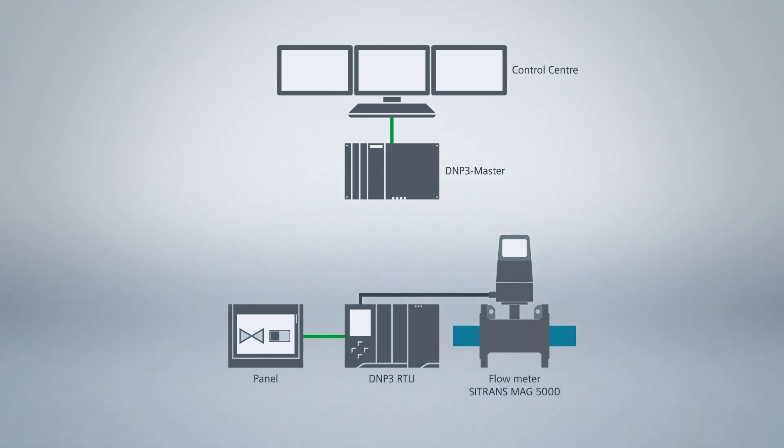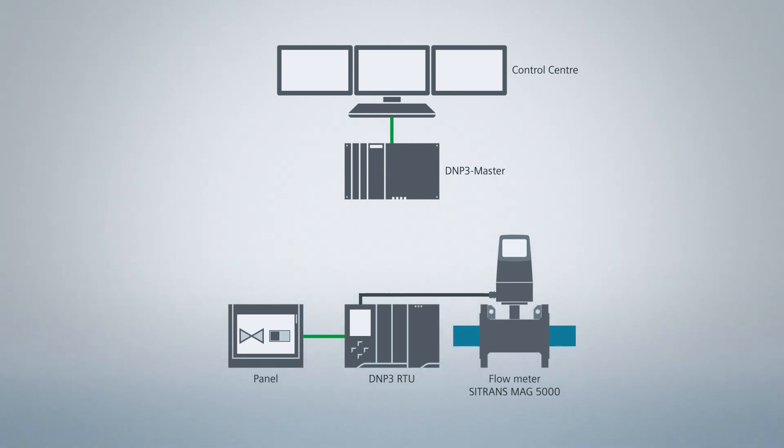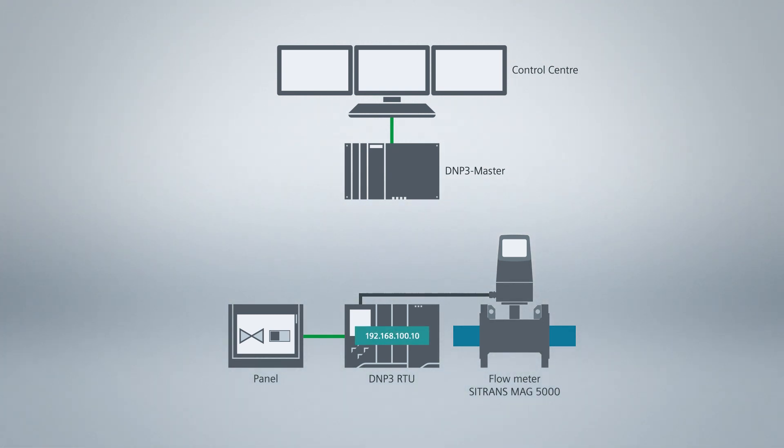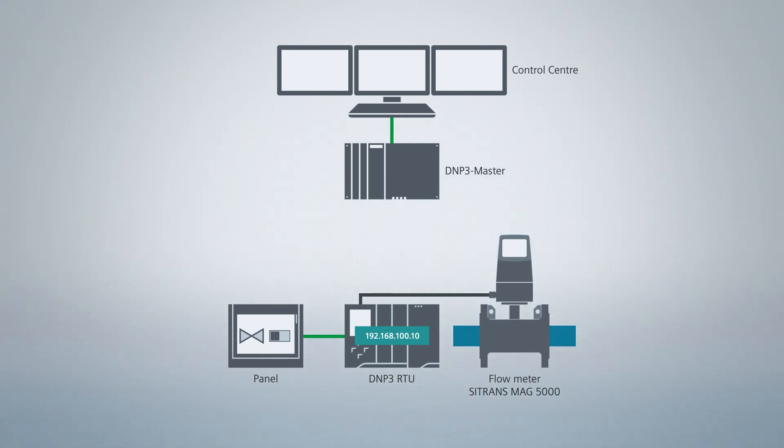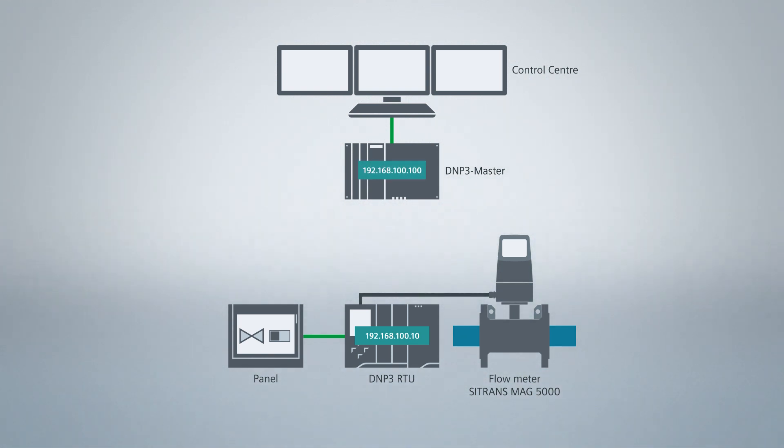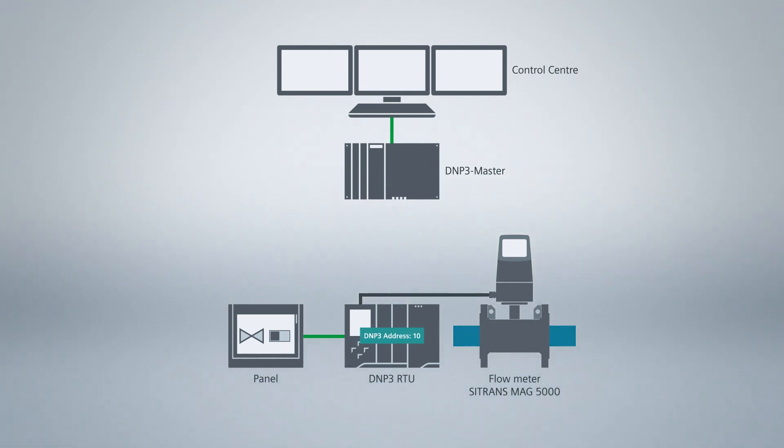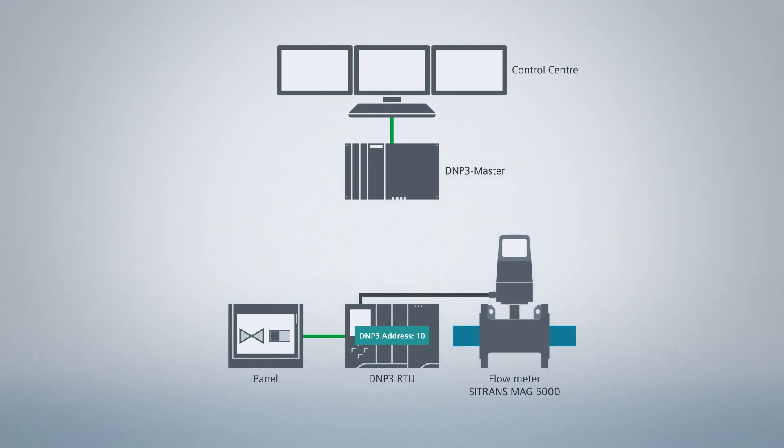As control system, a WinCC telecontrol project with DNP3 driver is pre-configured. Our DNP3 RTU has the IP address 192.168.100.10. The DNP3 master has the IP address 192.168.100.100. As DNP3 address, I use address 10 for the RTU. The DNP3 master operates under DNP3 address 1.